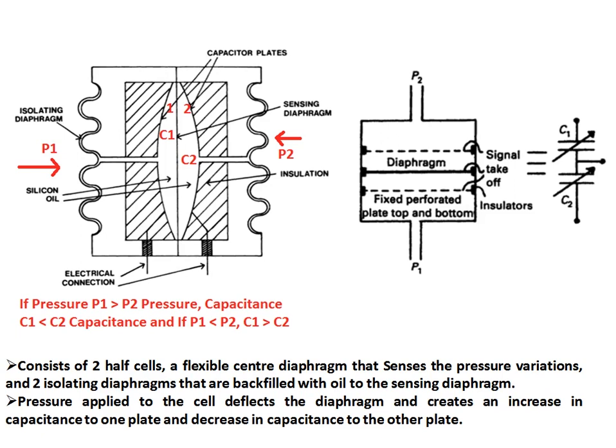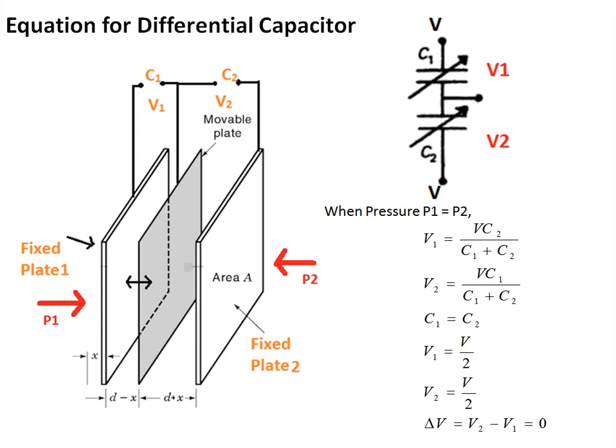The equation for the differential capacitance type DP transmitter is derived as follows. Whenever pressures P1 and P2 are equal, the voltages measured across the two capacitors are equal, and the differential voltage V2 minus V1 equals zero.